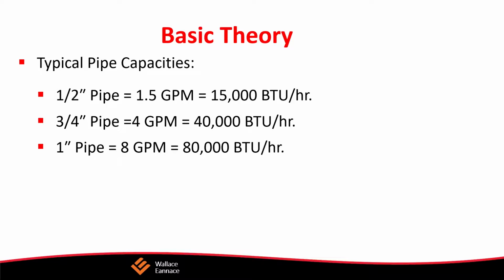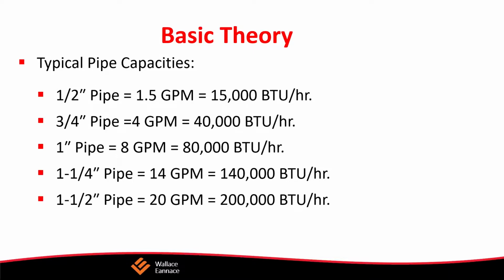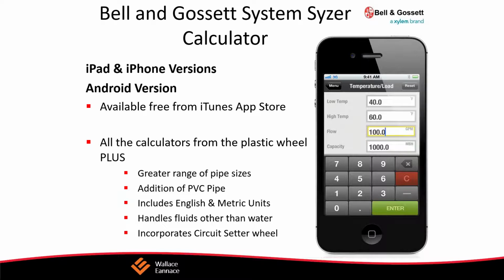3/4 inch will flow about 4 GPM. 1 inch, about 8 GPM. 1.25 inch, about 14 GPM. 1.5 inch, 20 GPM. And 2 inch, about 45 GPM.